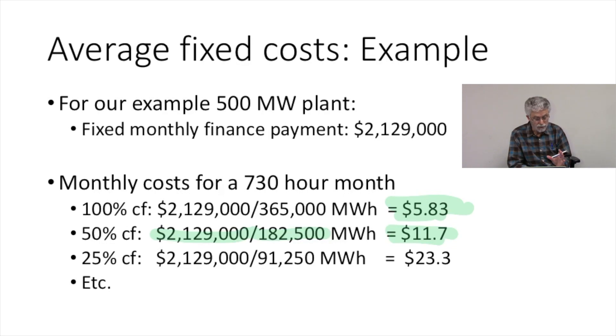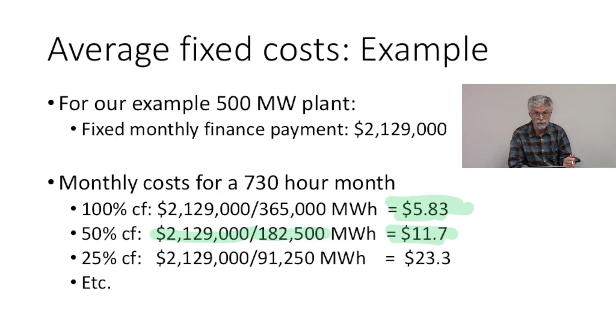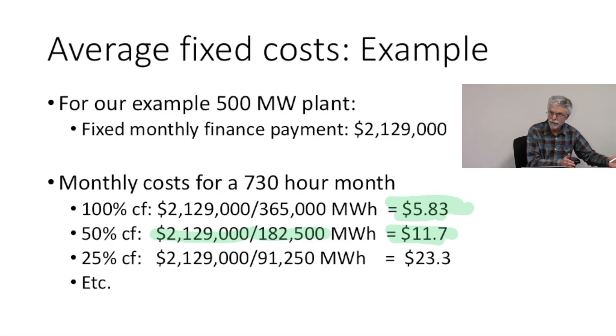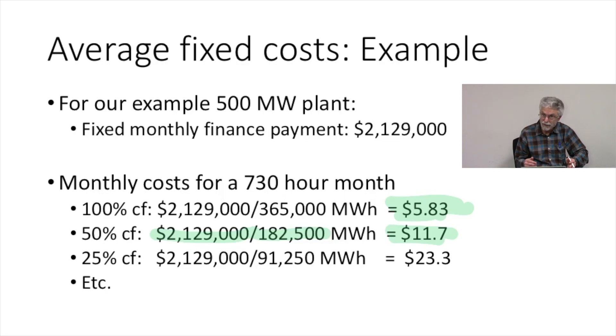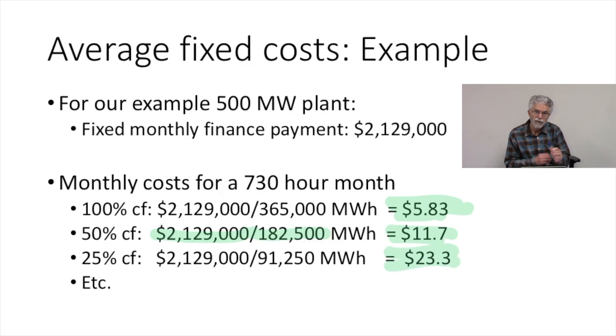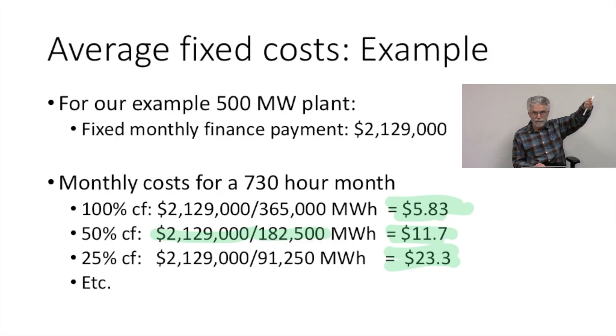If we further reduce the capacity factor to 25%, we're only going to generate a little over 91,000 megawatt hours. We still have our $2,129,000 fixed payment, but now we're only dividing it by 91,000 megawatt hours, and the average fixed cost goes up to $23.30. The lower the capacity factor, the faster the average fixed cost is going to go up.